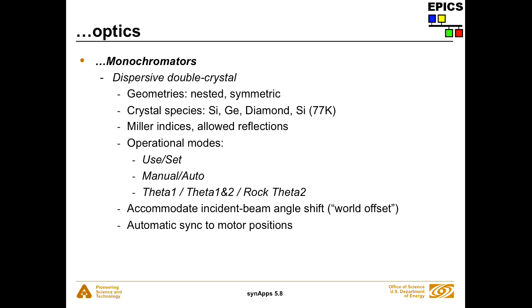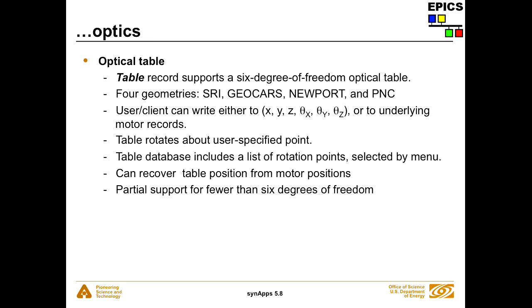The optics module also has support for a number of optical tables, mostly six-degree-of-freedom tables with four geometries. There are six virtual motors: X, Y, and Z translations, and rotations of the table about a fixed point. You can specify the point about which the optical table rotates, which is important for alignment — for example, you can scan until you get the beam into an entrance slit and then rotate the table about that slit. The geometries are entirely specified by the locations of the kinematic mounts and how the legs extend. They all support use/set so that after alignment you can call the current position zero.